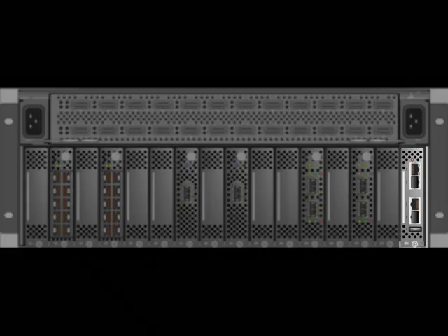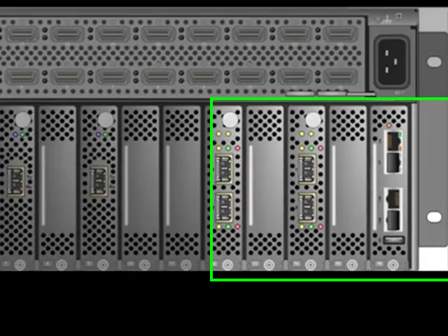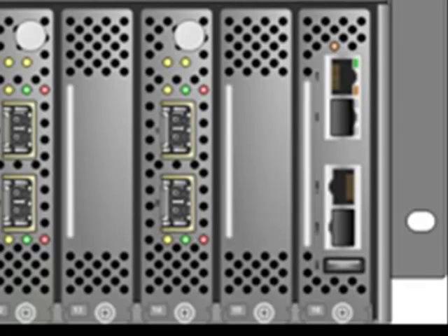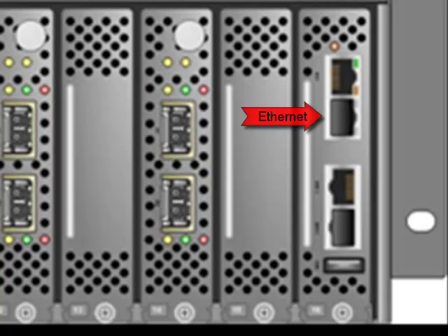That leads us to the discussion of cables and connections. Looking at the management module, we see a primary Ethernet and a primary serial port. Both can be used to manage the chassis, but the serial port is required to first configure the Ethernet port. That initial setup procedure is described in another online training session. The second Ethernet port is not used at all, and the second serial port may only be used for diagnostics.